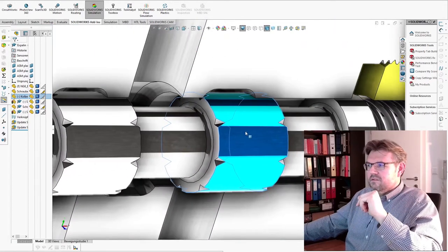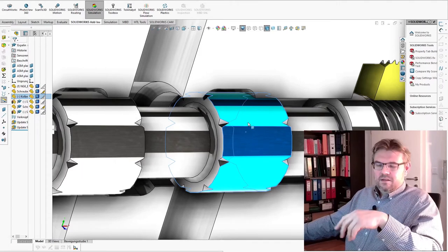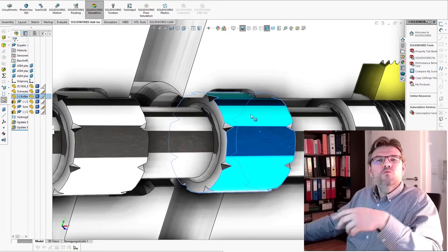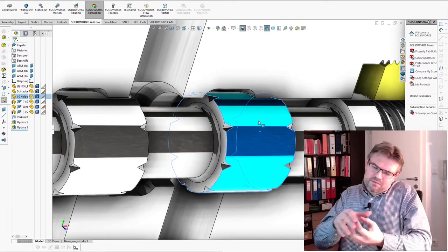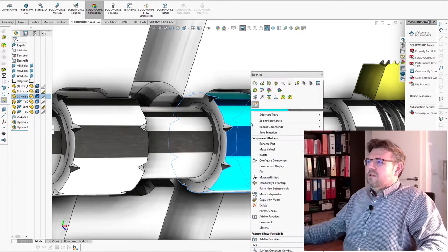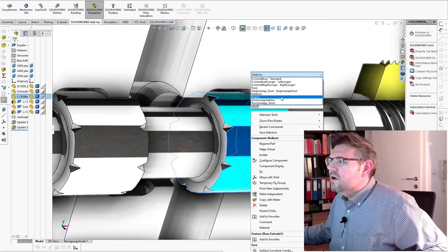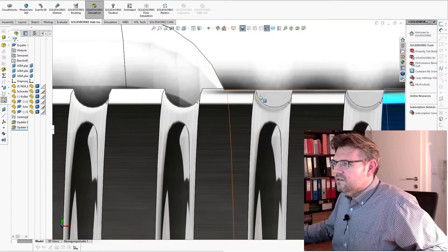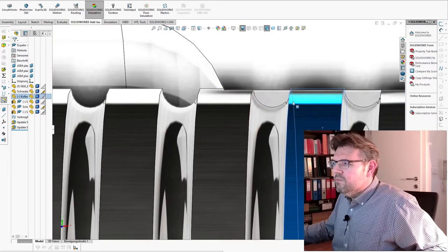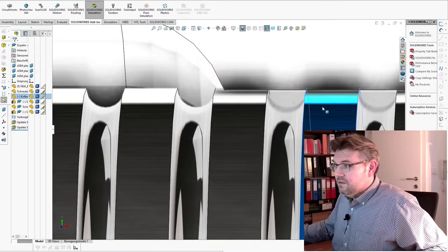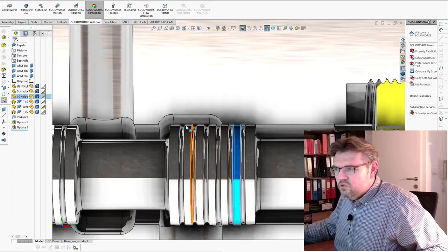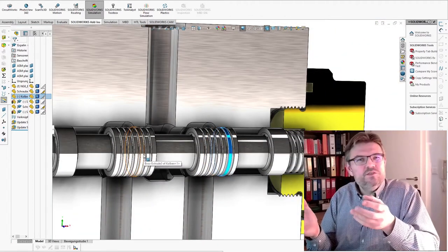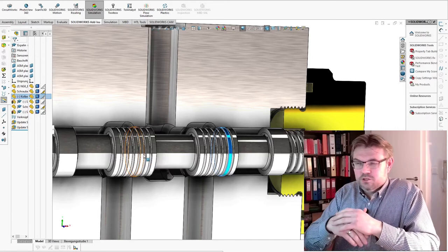And finally, those things here. You know, they need to be lubricated. If I have only a small way to travel, then there might be too little oil inside. There are also forces inside. This might get stuck to the wall. So it helps to have things like this. In those areas there will be an oil reservoir, and if this is moving a little bit, this oil is lubricating the part. So these little drills, these little notches, will help that the friction is getting less. So you see, there are a lot of tricks inside such valves.